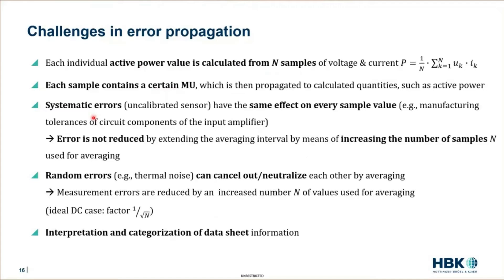This measurement uncertainty of each sample contains then some systematic errors and some random errors. So systematic error is, if you think about the manufacturing tolerance, perhaps a capacitor or resistance in the input amplifier of the data acquisition system is a bit too big or too small, and therefore the scaling or the offset is influenced. Then this error is the same or influences the measurement result on this individual channel for each sample in the same way.